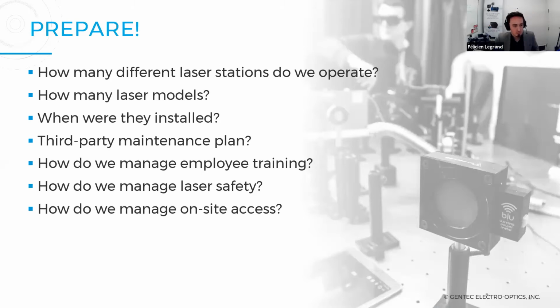Okay, so for service, we'll need to prepare, and you need to be sure what is most relevant for your reality. For example, keep track of those things. How many different laser stations do we operate? How many different laser models? Do I need a given detector that's different from one laser model to another, or can I use one detector for all? This kind of questions. And when were they installed? Typically for my application running 24/7 operation, do I expect the system to need maintenance after 3 months, 6 months? Let's measure and we'll see.